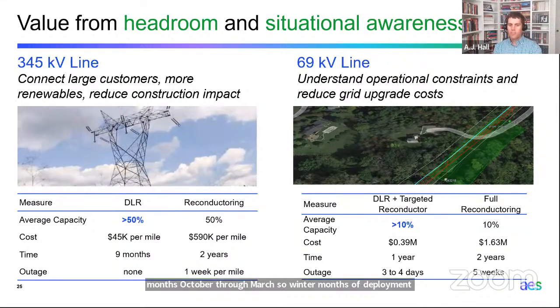You can see on the left that for 345 kV and larger lines, DLR is ready to scale right out of the box. These lines benefit from good wind conditions—they're higher up, have large right-of-ways, and don't make as many heading changes, which would require additional sensors to capture wind direction. Over the 6 months of deployment we achieved an average capacity increase of over 50%. To achieve something similar via reconductoring, we could have spent as much as $590,000 per mile, whereas DLR can achieve this at a fraction of that cost, about $45,000 per mile.